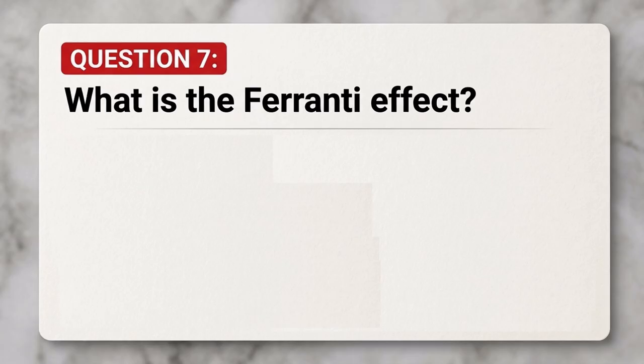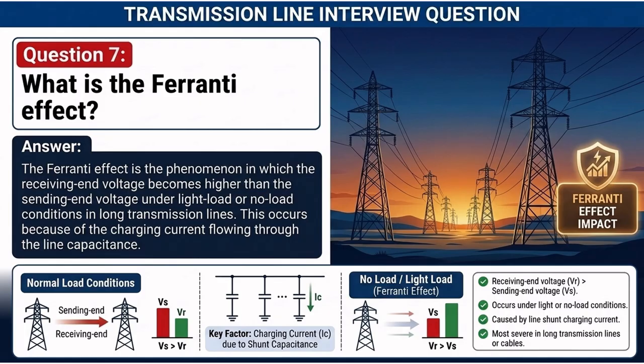What is the Ferranti effect? The Ferranti effect is the phenomenon in which the receiving end voltage becomes higher than the sending end voltage under light load or no load conditions in long transmission lines. This occurs because of the charging current flowing through the line capacitance.